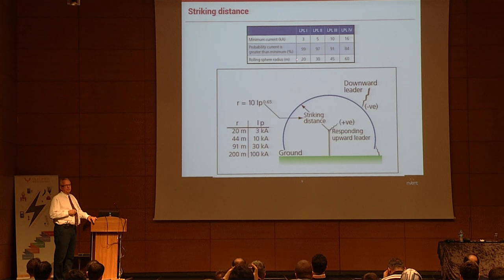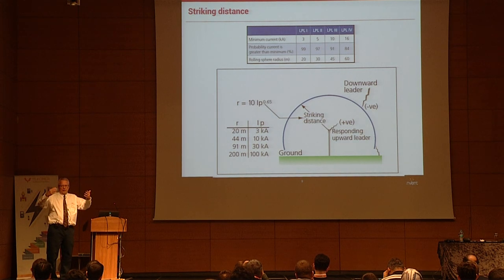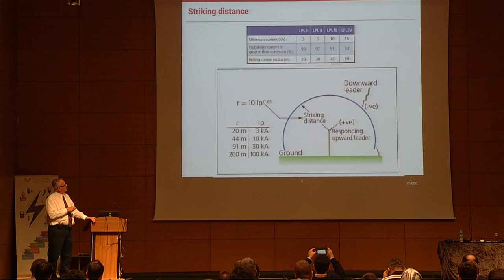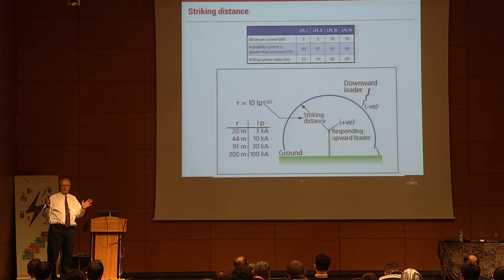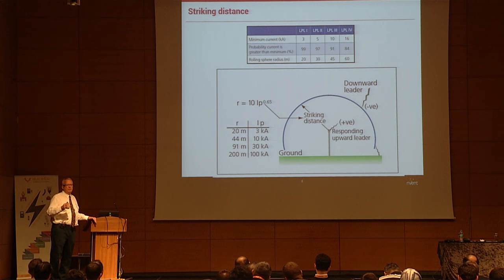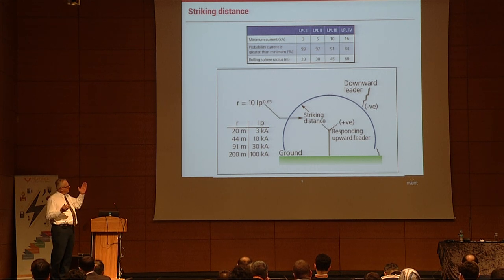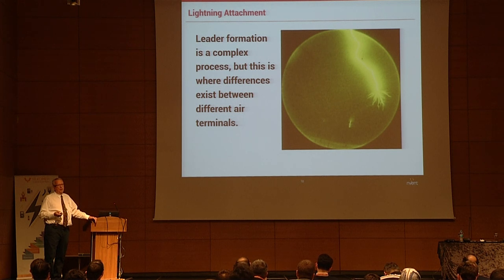For protection level one at 99% protection, applying the electrogeometric model — rolling a sphere with a radius of 20 meters over the structure — I still have a 1% chance that a 3 kA current will bypass my terminal and strike the structure. For protection level four, the bypass strike could be up to 16 kiloamps in intensity. That's where the protection levels come from. This laboratory picture shows how upward and downward leaders progress.